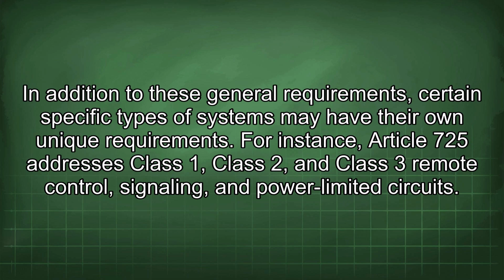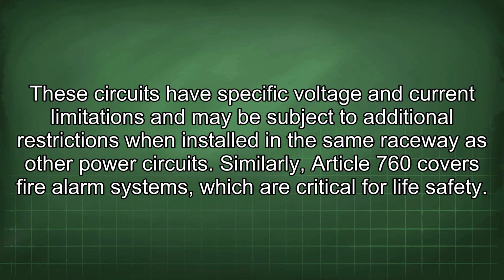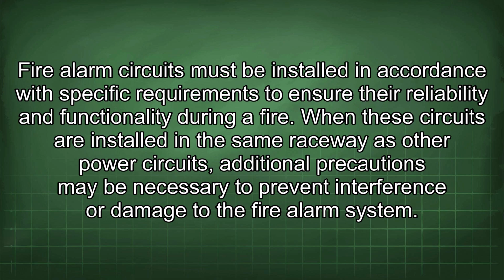In addition to these general requirements, certain specific types of systems may have their own unique requirements. For instance, Article 725 addresses Class 1, Class 2, and Class 3 remote control, signaling, and power limited circuits. These circuits have specific voltage and current limitations and may be subject to additional restrictions when installed in the same raceway as other power circuits. Similarly, Article 760 covers fire alarm systems, which are critical for life safety. Fire alarm circuits must be installed in accordance with specific requirements to ensure their reliability and functionality during a fire. When these circuits are installed in the same raceway as other power circuits, additional precautions may be necessary to prevent interference or damage to the fire alarm system.